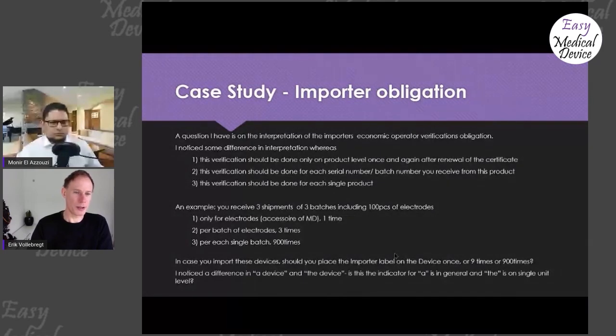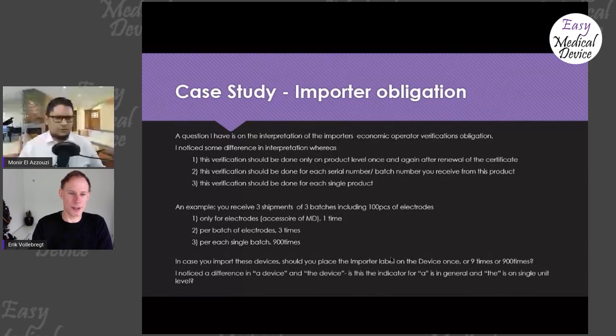The importer will know, because that's the procedure that they've agreed with the manufacturer, and the importer will also regularly audit that the manufacturer actually does this. So that means that I think then you have a procedure of which you can say, I have verified that this is true for every product. Because, use your big person brain, if you look at, for example, manufacturing of devices under a full quality system, that also doesn't require that you inspect the production quality for every medical device, right? It doesn't say that the notified body, for example, has to inspect every finished device. And this works the same way. You set up procedures that are done in a way that they consistently lead to the outcome that is legally prescribed. And that's how you do it.